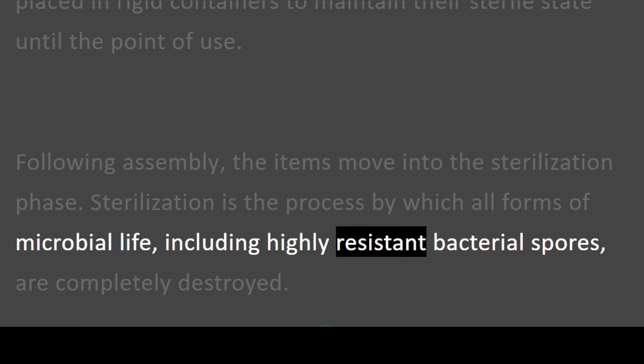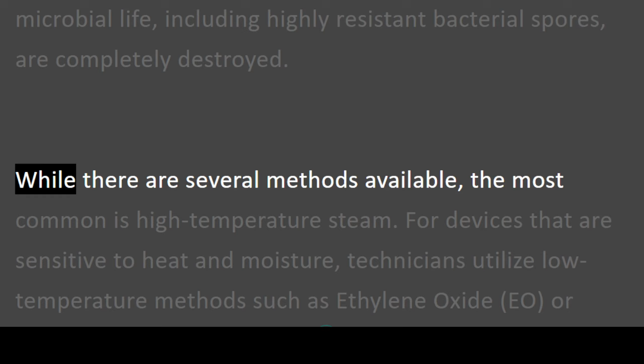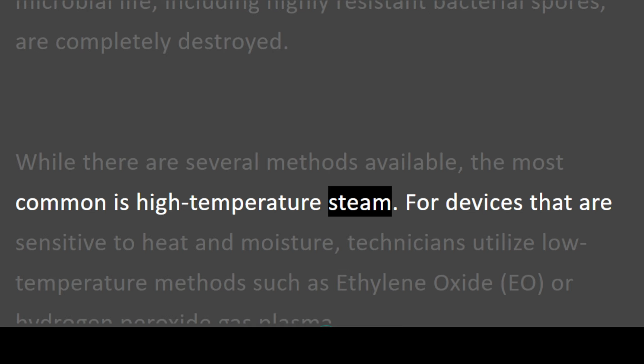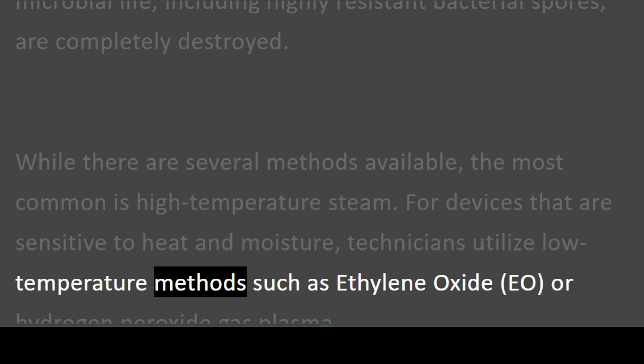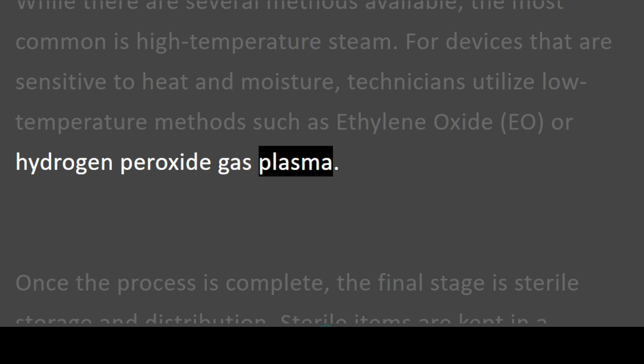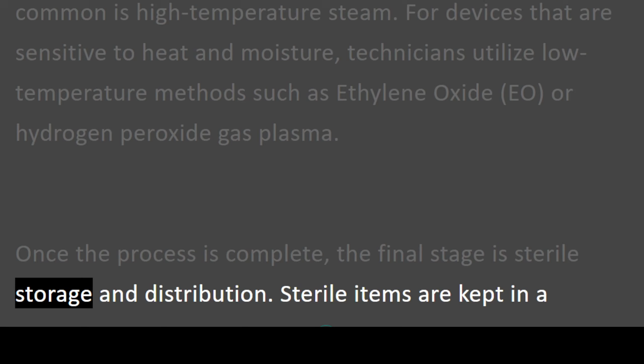Sterilization is the process by which all forms of microbial life, including highly resistant bacterial spores, are completely destroyed. While there are several methods available, the most common is high-temperature steam. For devices that are sensitive to heat and moisture, technicians utilize low-temperature methods such as ethylene oxide, EO, or hydrogen peroxide gas plasma. Once the process is complete, the final stage is sterile storage and distribution.